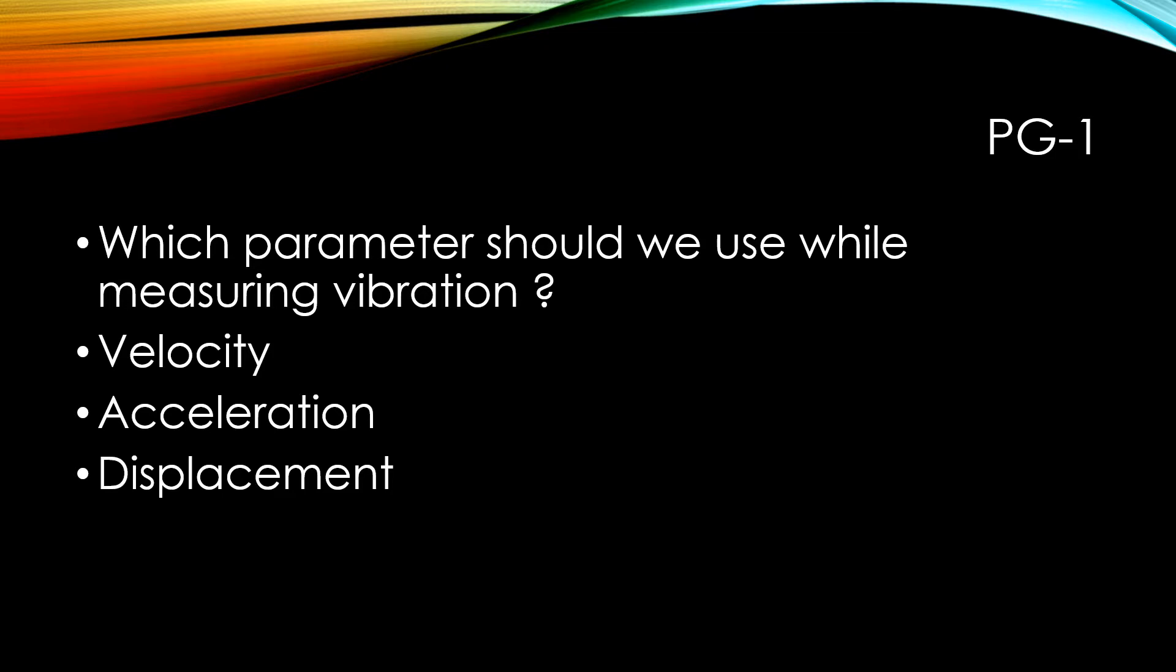The motion below 10 Hertz produce very little vibration in terms of acceleration, moderate vibrations in terms of velocity and relatively large vibration in terms of displacement. So we are going to use displacement as a parameter in the motion below 10 Hertz.